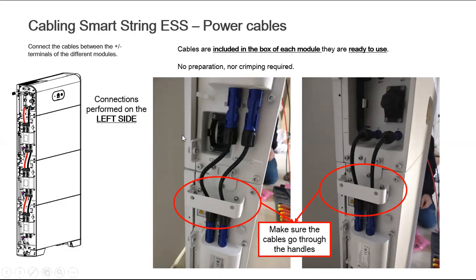Also, the second thing I want to mention here is to always make sure the power cables pass through the handles of the power control modules. If you put the power cables over the handle, there will be a problem installing the covers on the battery. If you go through the handles, then you can fix the covers quickly and properly.